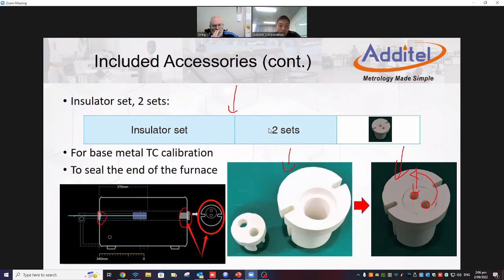And for the base metal testing, as you can see from the picture, we have the insert cap design. On this side we use this insulator to seal. We still have two small holes right here. Normally it doesn't matter, but if the customer really cares about that, they can use ceramic fiber to seal the two holes. That's for the high temperature. So this is one side of the furnace. The other side, same thing. We need to use the ceramic fiber to seal this point. In this way, we have no heat leakage from both sides of the furnace.